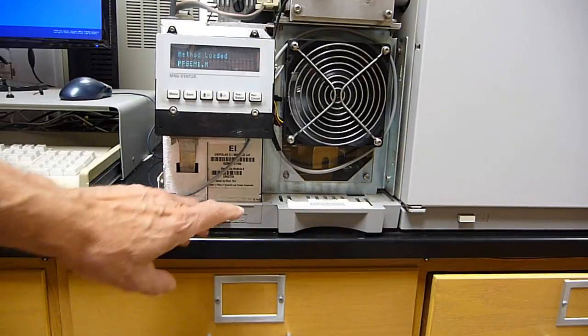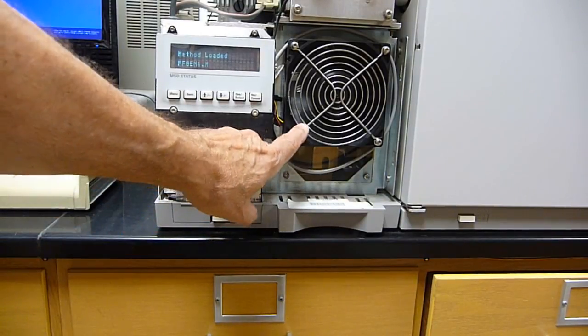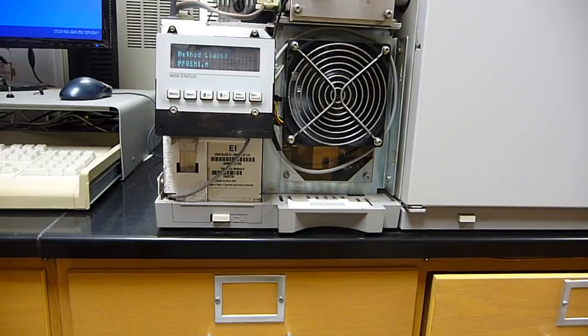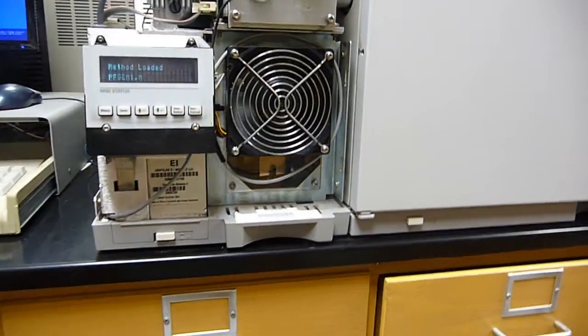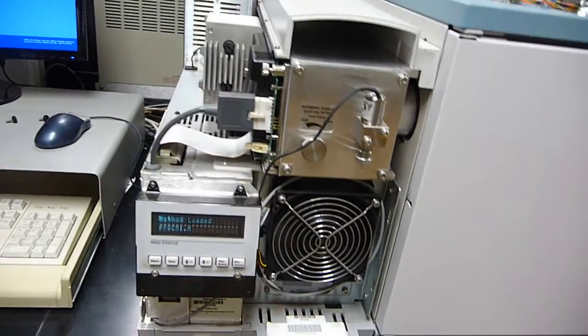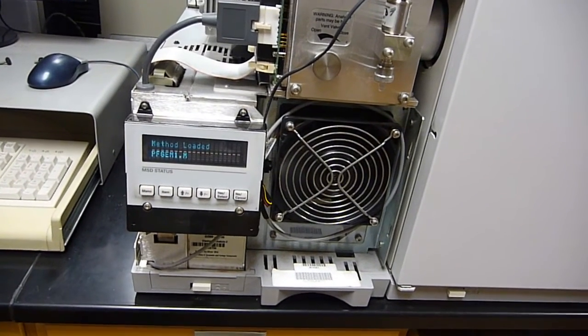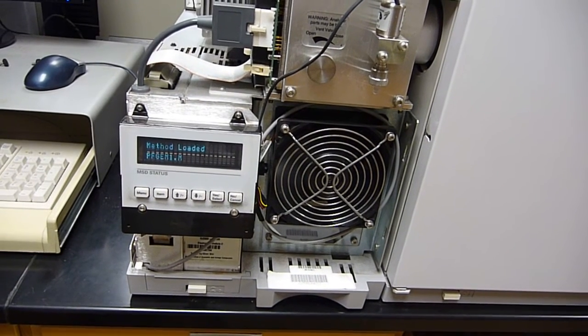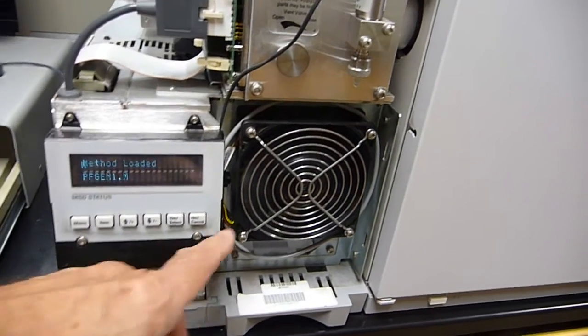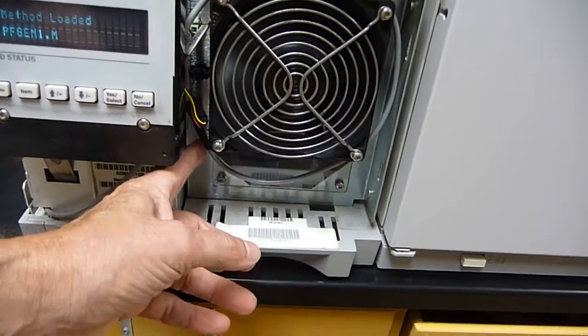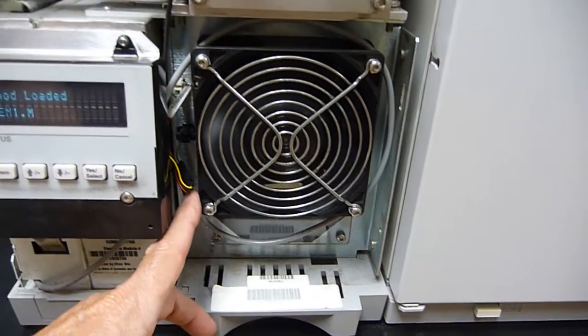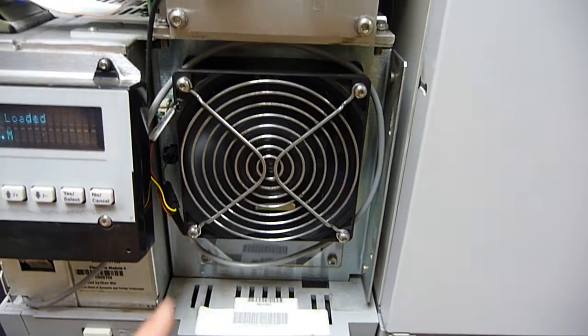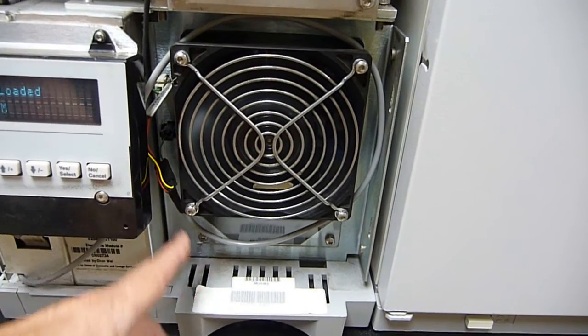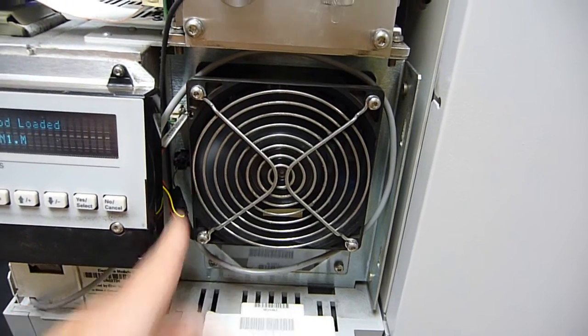And as an aside, in order to power this fan separately from the instrument control, it's not that difficult at all. What it requires is a UPS and then an AC adapter. That's going to put out the appropriate voltage to here. And then you need some connectors because this one has an RPM signal. So if the RPMs drop below 90%, it's going to turn off the heater. So you want to get that information back to the instrument chassis.